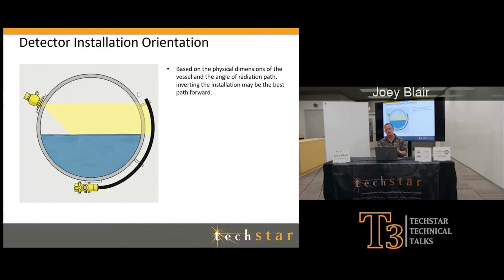So a good installation practice is to invert it. You'll have the bottom end of your fiber bundle and the head at the 0. You don't have to do that, but it does give you a more linear measurement. When I say linear, I mean there are more possibilities of just being able to do an open and closed shutter. The gauge will be able to calculate, if I just take a 0 point and a 100% calibration point, the measurement will be very linear throughout the field. So when the gauge says it should be 10%, I'll be close to 10%. When it says 20, I'll be close to 20. You don't have to do as many calibration points in between.